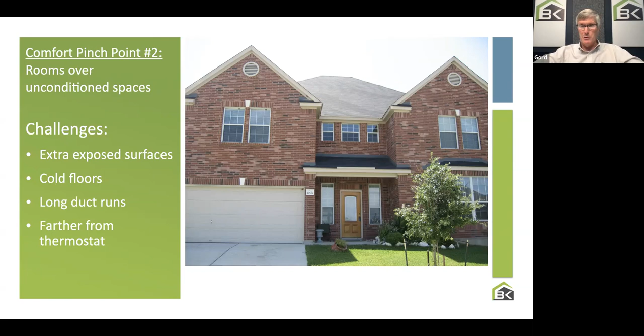Notice the thermostat is way over in the middle of the house, and that bedroom—how much air does it need? You really need to think about it: if the temperature coming out of that duct is 10 to 20% lower than the temperature coming out of the duct in the kitchen, I need 10 to 20% more air getting to that room. And my furnace system has to be at really good pressures.